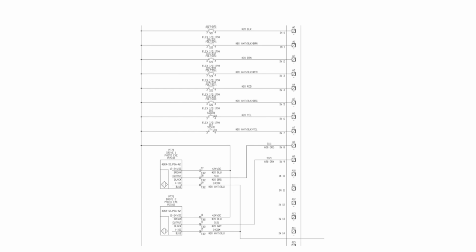Inputs in the field going to a PLC. So when I push down on this, that 3 and 4, it closes the circuit, and through some kind of programming, either runs the motor or puts it in a ready state, and then you hit another button to start it. And underneath here, you see something called photo eyes. Again, a sensor sending out a beam of light, 24 volts DC in, and when I close my 24 volts, it sends an output out of the sensor to the input of the PLC card, saying, "Hey, I'm blocked."